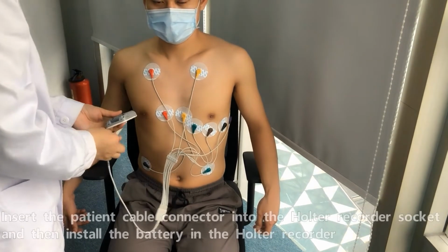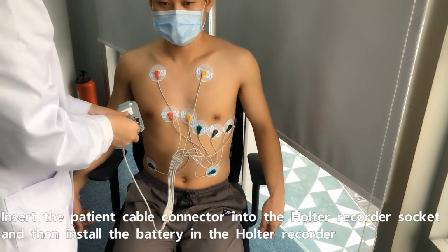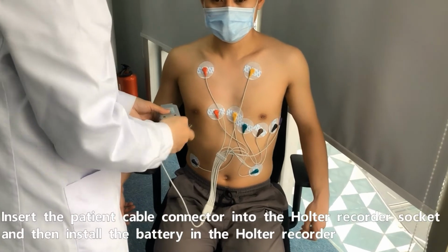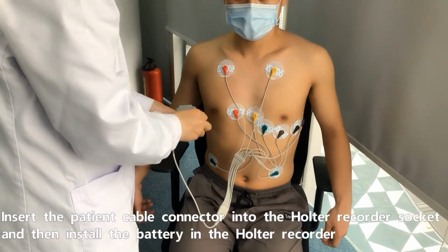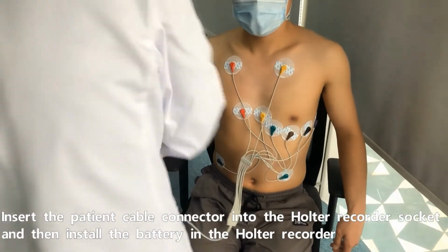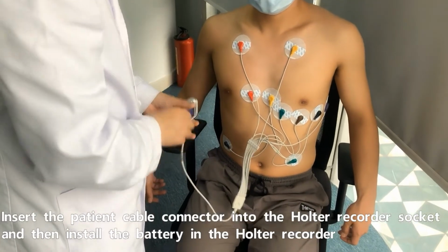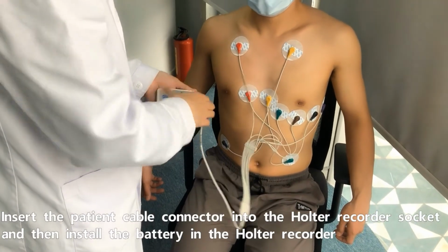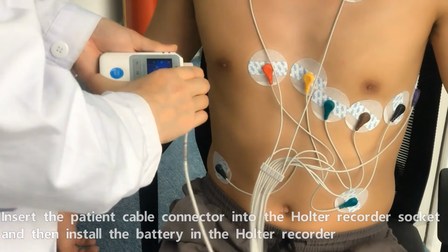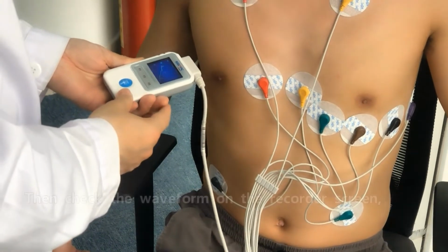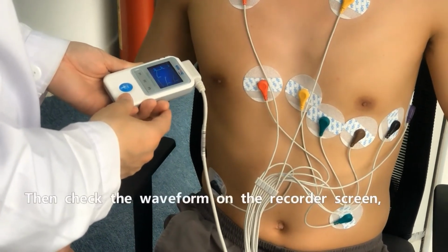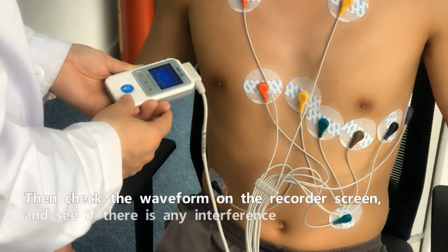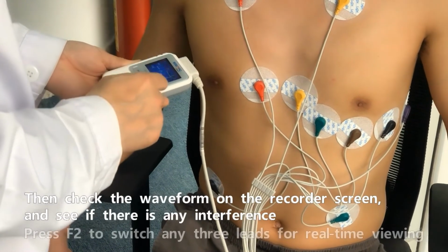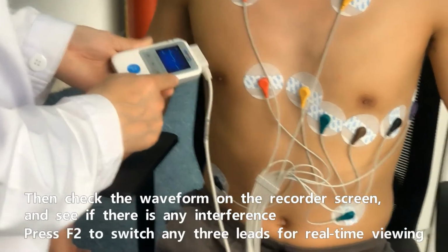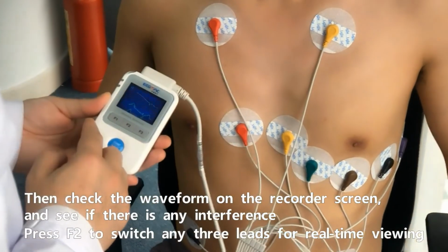Insert the patient cable connector into the Holter recorder socket, and then install the battery in the Holter recorder. Then check the waveform on the recorder screen and see if there is any interference. Press F2 to switch any 3 leads for real-time viewing.